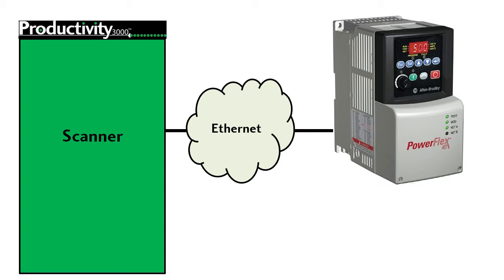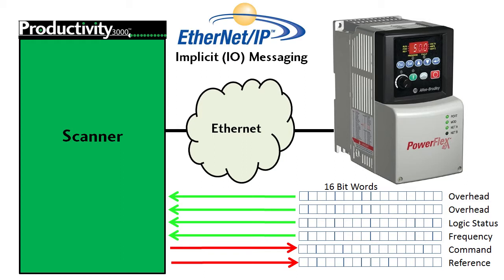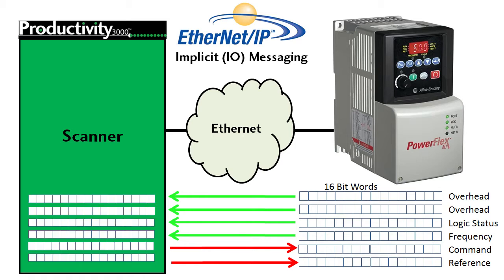Our goal is to have all the data between the Flex drive and the Productivity 3000 transferred in the background so our ladder code doesn't have to fool with controlling all those transfer details. That's exactly what the implicit or I-O messaging of the Ethernet IP protocol does. Once you set it up, it automatically maintains the data transfer for you, so your ladder code can just deal with local data.